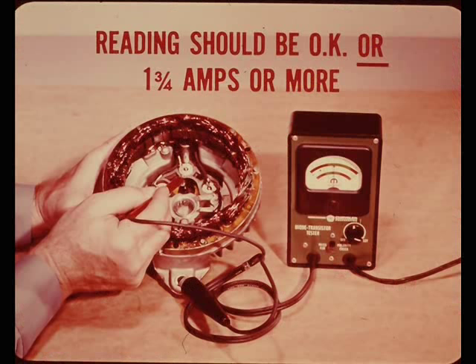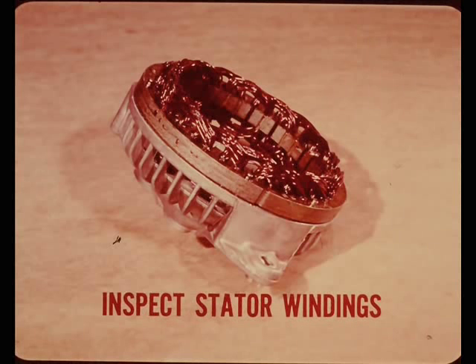The reading for a good rectifier should be okay, or 1 3/4 amps or more, and about equal in each group. A shorted rectifier reads near zero and causes the remaining good ones to read low. An open rectifier shows about 1 amp, with the others in the acceptable range. If you find open rectifiers, be sure to inspect the stator windings for burnt areas or signs of overheating. This overheating usually results from a short-circuited stator winding, which also overloads the rectifiers.